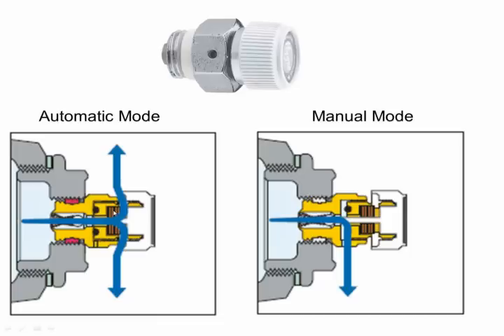Now, what is this air vent? It's actually an automatic air vent that relies on hygroscopic sponges, if you will, to cause it to operate automatically. So here in the automatic mode, if we get a buildup of air underneath our air vent on our heat emitter, the air, because the system's under pressure, will push up through these series of sponges. They're actually little discs, and there are spaces between these discs when it's in the dry mode, pushing the air out. And after the air is expelled, if moisture comes in behind it, the sponges absorb the moisture, they swell up, and they close off any further passage, thereby acting automatically. Next time air starts to accumulate here, they dry out, and it repeats the process all over again.